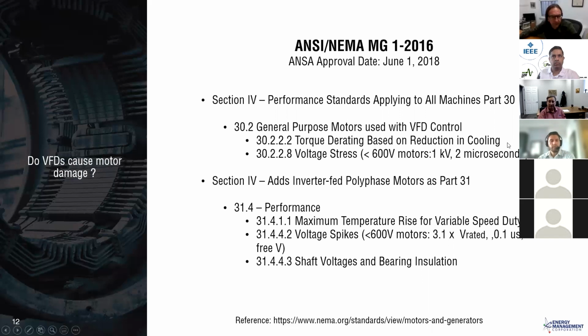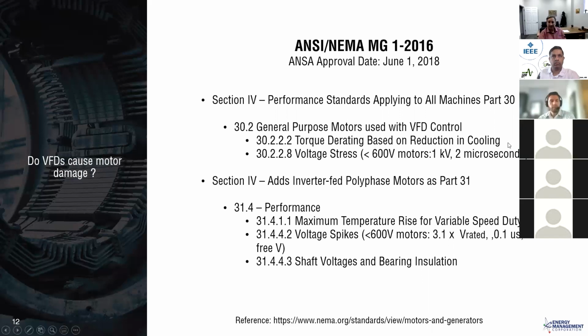The torque derating from a cooling standpoint could be very detrimental if you have a constant torque load like a conveyor and put a motor on that's only rated for maybe a 4-to-1 ratio, and you're now turning it down 10-to-1 ratio, you're going to run into cooling problems. And so that's addressed in 30.2.2.2, cooling issues associated with reduced speed applications with inverters. And for those motors, they're saying basically, if you can make sure that a motor that is a less than 600 volt class motor, so our 480 volt motors, under medium voltage motors, that if you can have the voltage stress or the waveform that the motor sees less than 1 kilovolt and more than 2 microseconds of rise time, you should be okay. There should not be an issue.